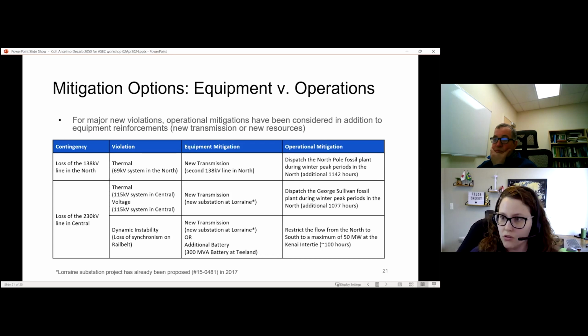But we can also mitigate this problem if we have local generation on the 115 kV system. One example would be to dispatch more hours of the George Sullivan fossil plant when we have peak load during winter. However, we saw that the loss of this line also causes dynamic instability on the system, and generation redispatch won't do the trick here.